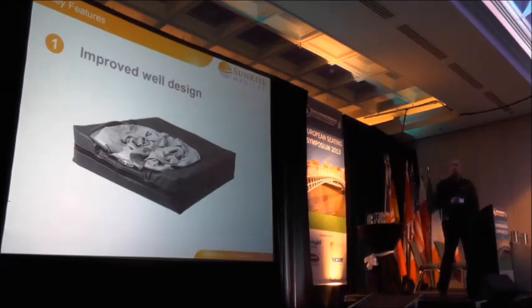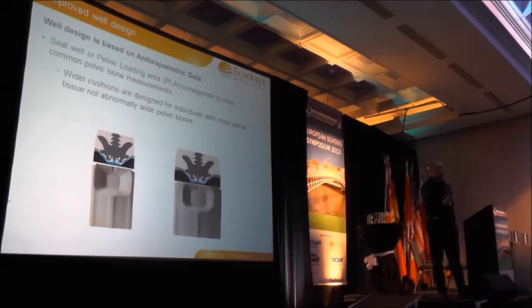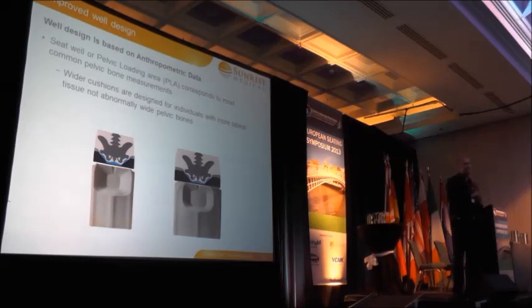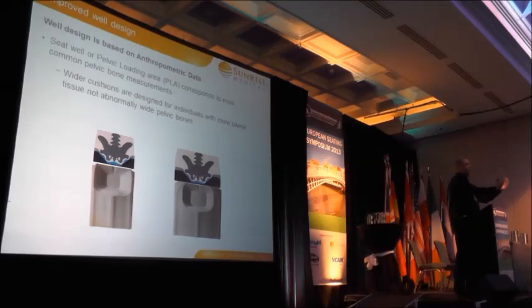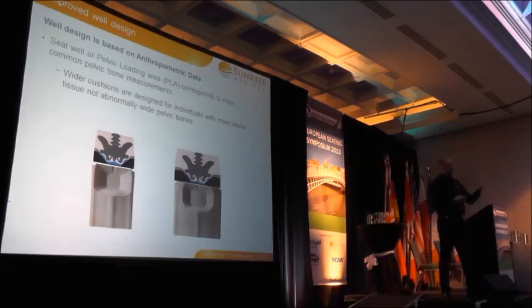One of the big things we've done is look at the well design. We took the very good information that came from the J3. When we designed the J3, we looked at anthropometrical data studying the width of people's pelvises — the measurement between the ASIS horizontally to the opposite ASIS. From that, we noted a certain percentage of people's common pelvic widths, and we were able to work out that 95% of people fall into three different well sizes. The remaining 5% who don't fit are cases of abnormal bone growth — good information drawn from hundreds of thousands of skeletal measurements.